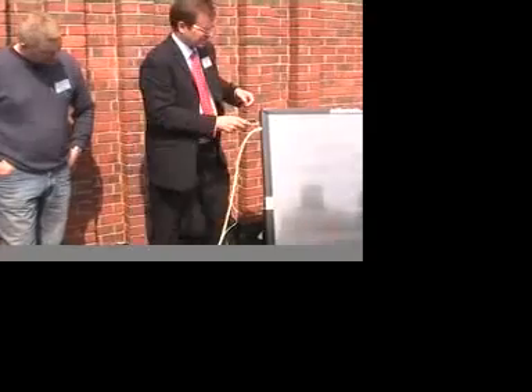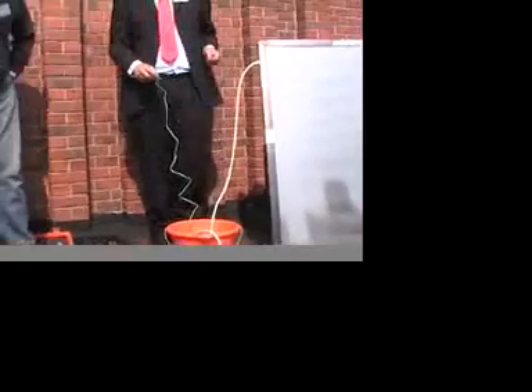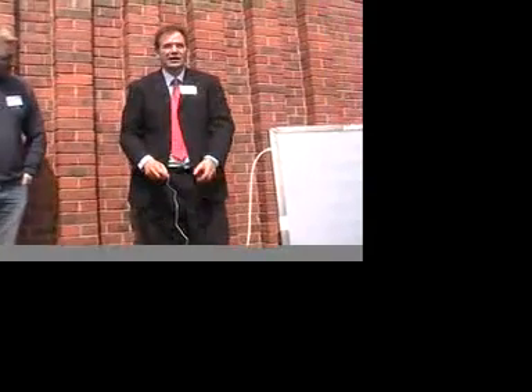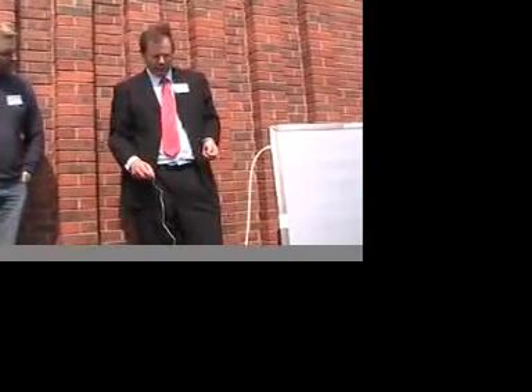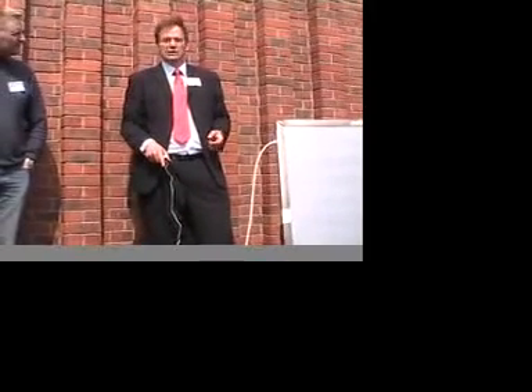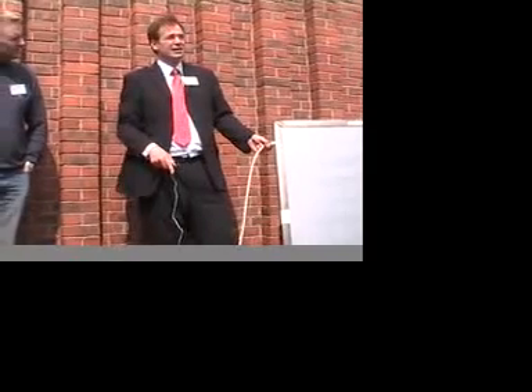What we're doing now is the priming process — blowing the air out of the pump. If you were doing this in a house on a sunny day and you were priming it, you would actually be hearing that glug, glug, glug at the end of the vent. This pumps at peak flow about two-thirds of a litre per minute, so in about three minutes we should pump the air out and get a slug of particularly hot water.